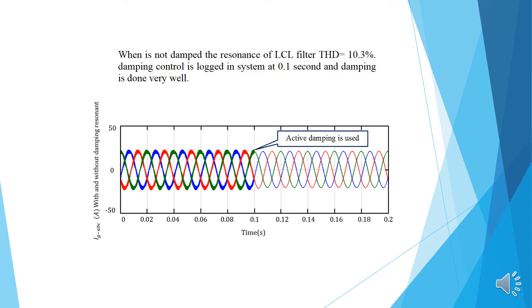In this case, damping isn't applied until 0.1 second. The THD has been over 10%. After applying damping in the system, the grid current status has been improved and damping is done very well.